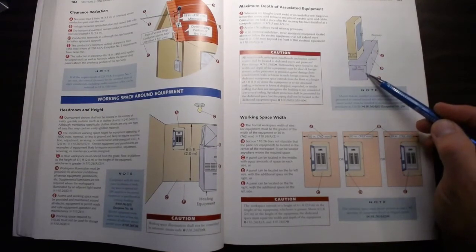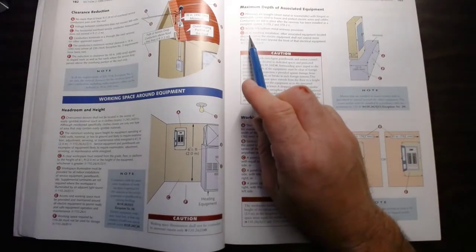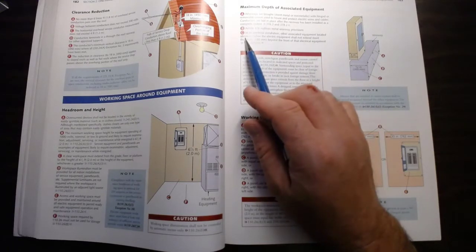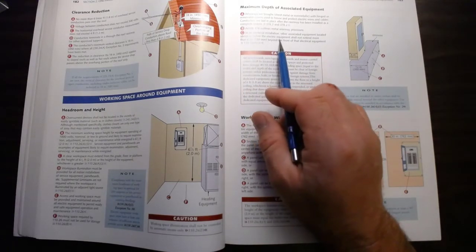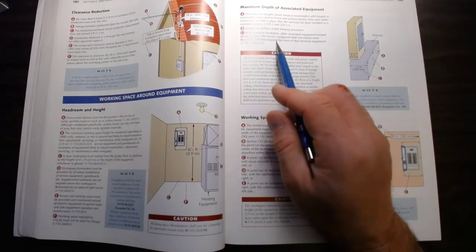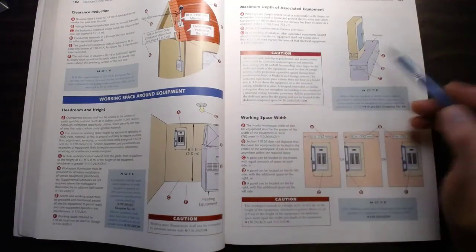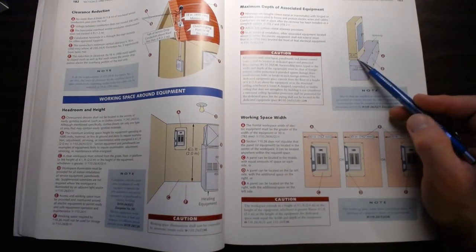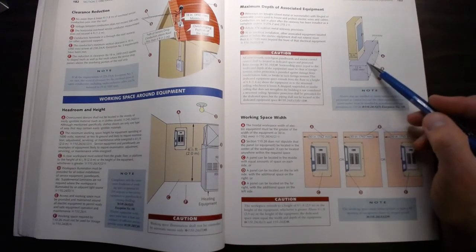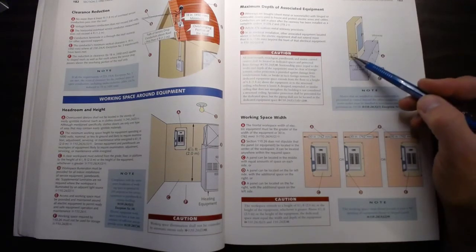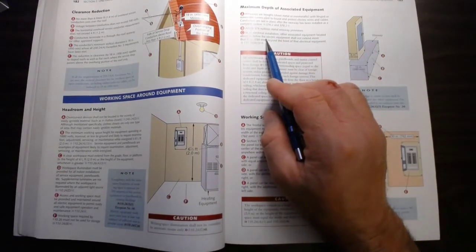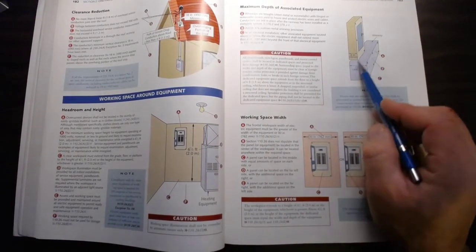When we look at the maximum depth, it says here that in the electrical installation, other associated equipment located above or below the electrical equipment shall not extend more than 6 inches beyond the front of the equipment. So if the panel is 6 inches deep, then it's 6 inches from there. That's 12 inches that this gutter or wireway can be at the depth of. So this is a good one to remember, and something again to write down in your Ugly's book when you're building these types of installations.